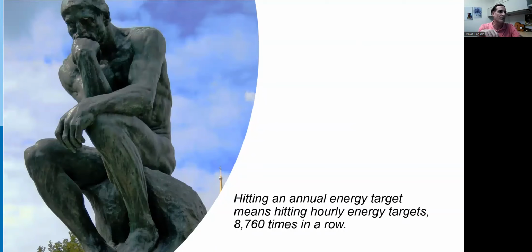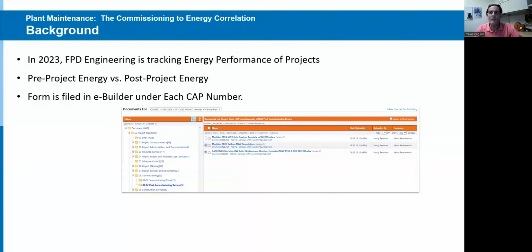So we've had to force a very deliberate design approach. The mechanical engineer should know that if it's October, 74 degrees outside, and 10 in the morning, they should know how much fan power their system is supposed to use at that time, and then we measure it against that prediction. That's a very different vocabulary than what the design community is used to, but it's what you need to validate performance.